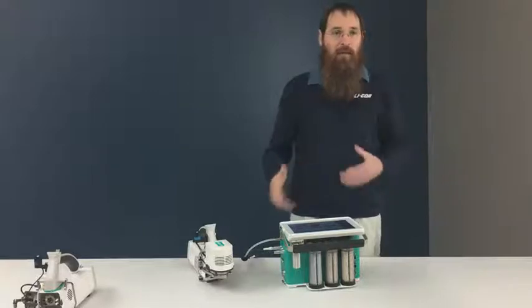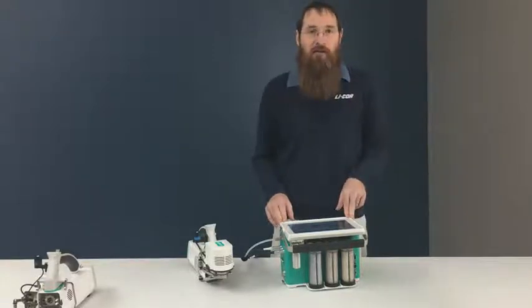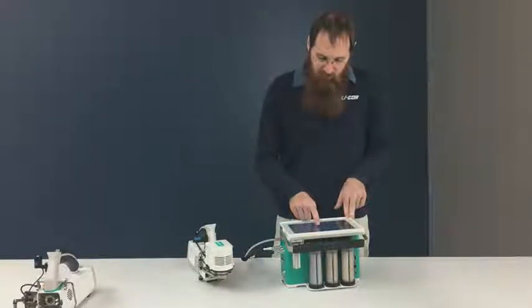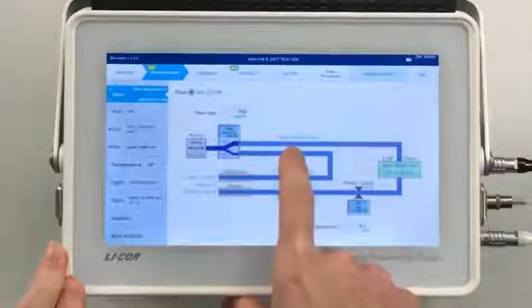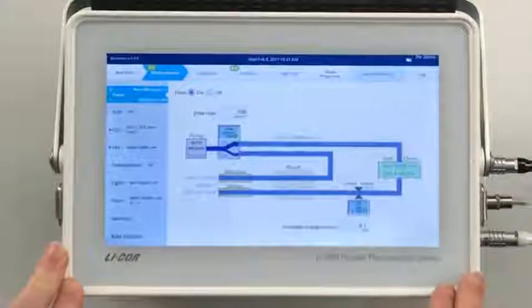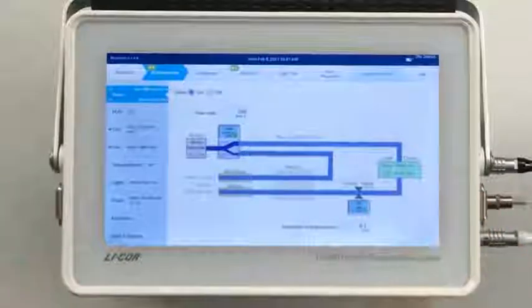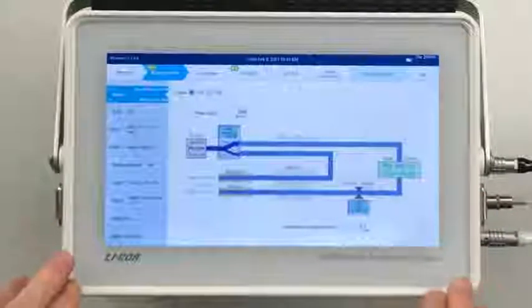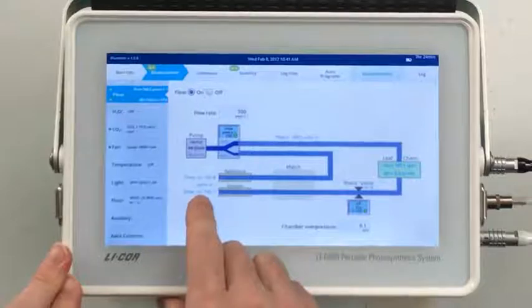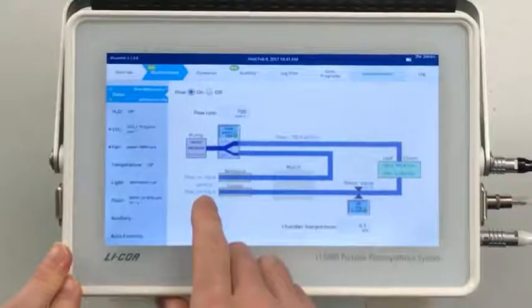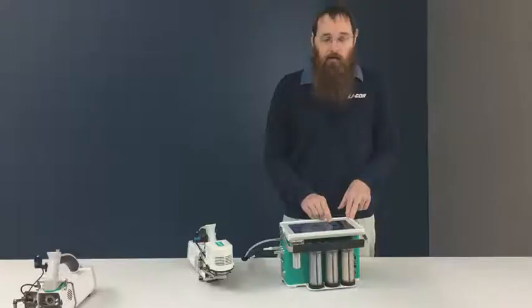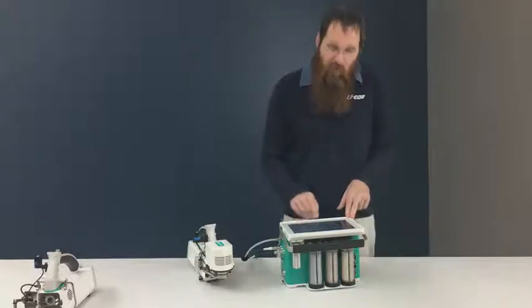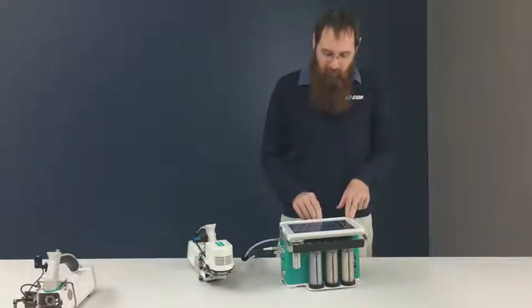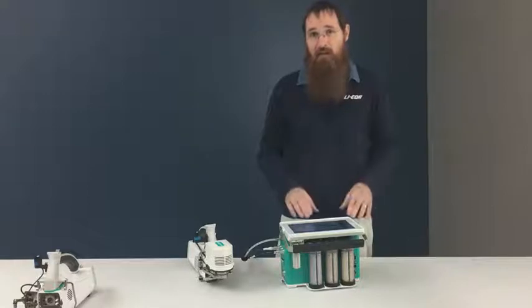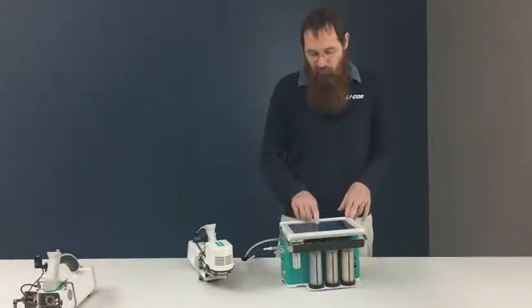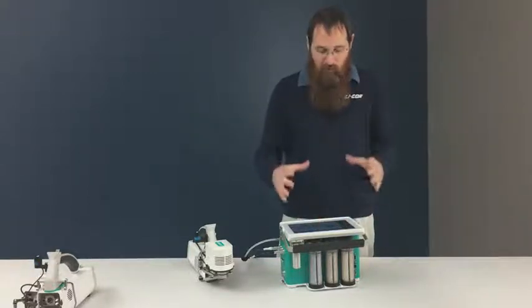I said something about having extra sensors, more than what we need for calculations. One of them is this, right? So I have this sensor measuring flow going into the sample chamber. That's what we use to compute assimilation and transpiration, right? But I also have flow sensors on the outflow from the two gas analyzers. And because I know flow going into the chamber and flow coming out of the chamber, I can compute an approximate leak rate, right? The flow meter going into the chamber, that's a high resolution flow meter.